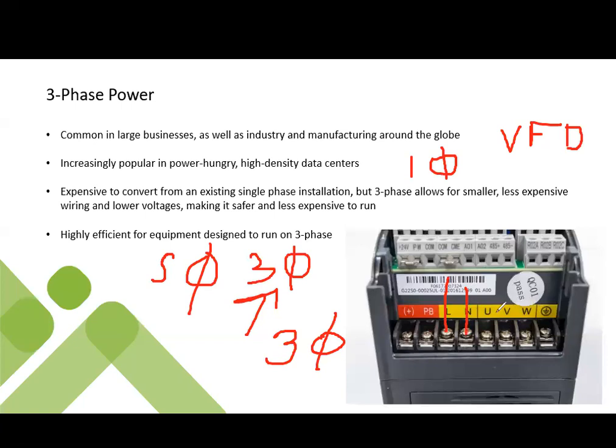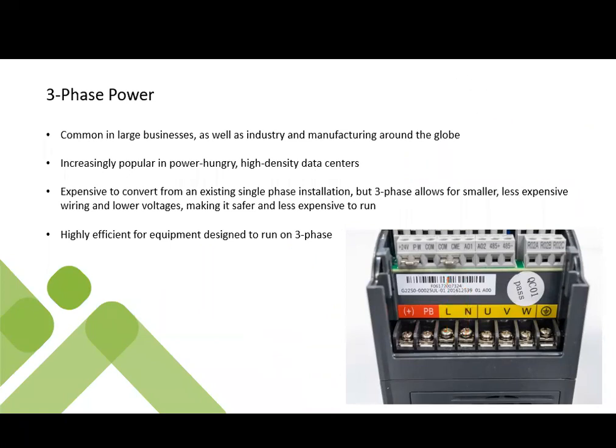So this particular drive gives us a choice. When I bring in the single phase on the back end of the drive, it will deliver three phase to that piece of equipment. And that's very economical to do. Plus, you get speed control. So a lot of times, if we only have one piece of equipment and we don't want to convert our whole single phase system to a three phase system, we could pick up a fairly economical VFD and definitely have three phase on the load side of that drive.